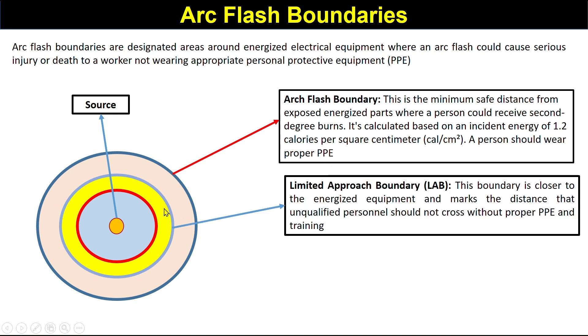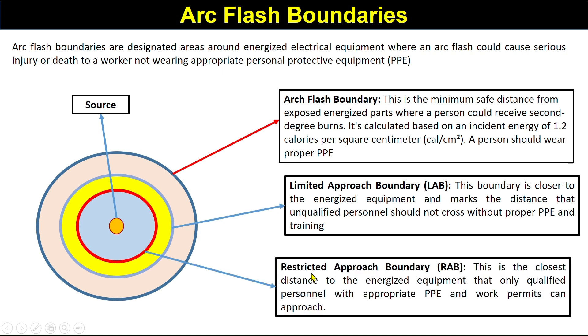The limited approach boundary is closer to the energized equipment and marks the distance that an unqualified person should not cross without proper PPE and training. The restricted approach boundary is the closest distance to the energized equipment — only a qualified person with appropriate PPE and a work permit can approach this zone.